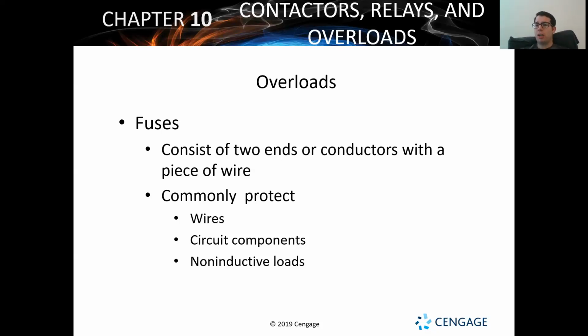So with power disconnected, check on continuity. Check the two sides of your fuse and just listen for the beep. You don't hear a beep, bad fuse. You hear a beep, good fuse. That's pretty much all there is to testing them. But you're going to replace a lot of fuses, because this is one of the most common parts that fail, someone at the breaker trips in their house.